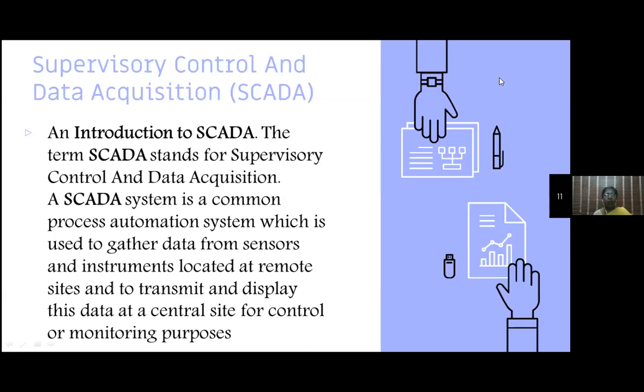So what does it supervise? It collects data from the field, from sensors and all the equipment available, and then produces a report based on the data collected. It can give a display, a trending of the variable, we can write a script to mimic a given process, and it can generate an alarm under emergency conditions.